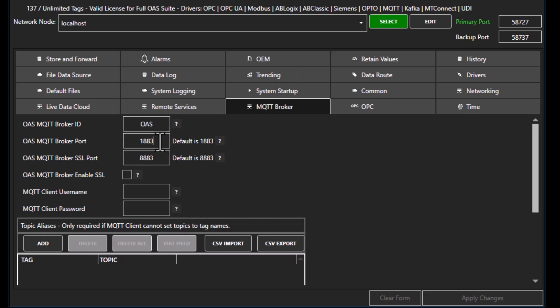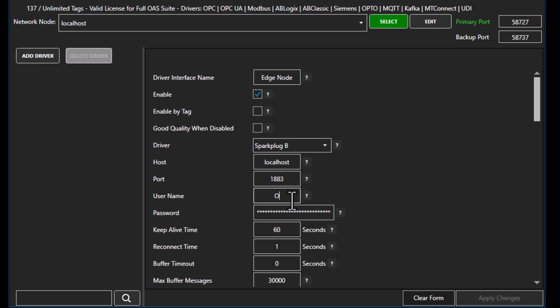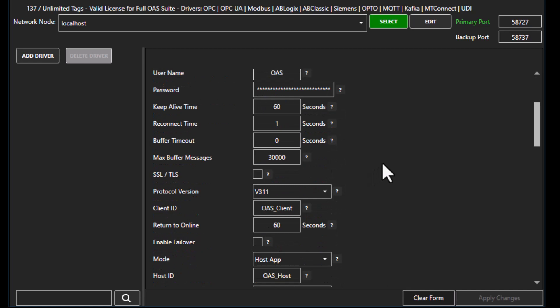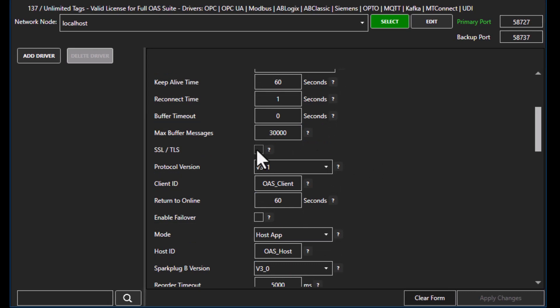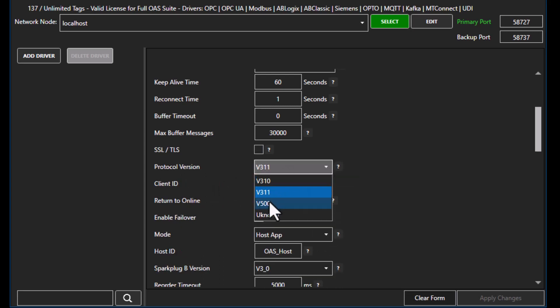You can turn off the OAS broker under Configure Options by going to the MQTT broker section and changing the broker port. We've used HiveMQ and Mosquitto for testing — they work very well — but in this demonstration I'm just going to use the OAS built-in MQTT broker with localhost. There is authentication set up for tag access, so I'm going to use a username and password for read, write, and browse access. You can optionally enable SSL for a third-party secure broker, setting up a certificate from a certificate file or private key file on Windows, or using a PFX file on Linux. The protocol version can be set to either 3.11 or 5.0.